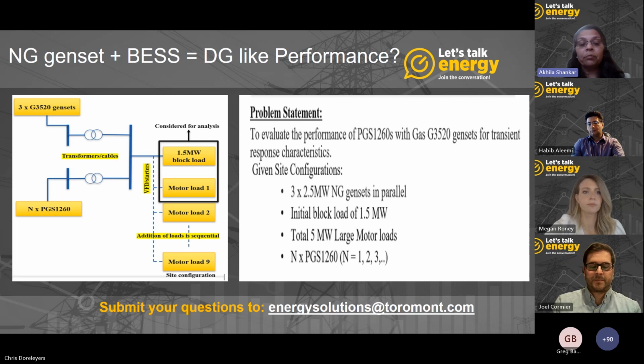So in this case, three 2.5 megawatt natural gas gensets operating in parallel were subjected to a block load in the first step of 1.5 megawatt. And subsequently, the customer wanted 9 800 horsepower motors to start in 9 steps. The customer's requirement was that whenever the emergency gensets are operating, the battery energy storage system should support the transient block load and motor starting requirements. Once the emergency system has reached its steady state operation, then the battery energy storage is not required and it could be recharged, pending, of course, the generation capacity. Under normal power conditions, when the genset is off, the battery energy storage system is not required again and it can recharge. If we can go to the next slide, please.